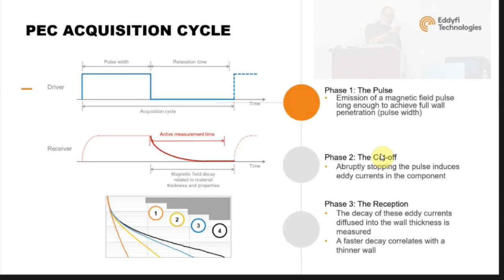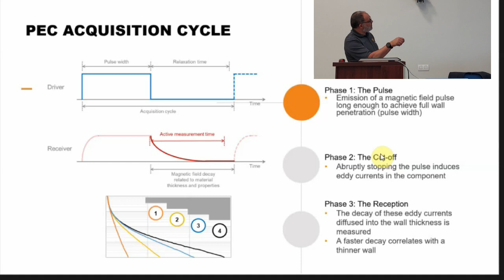So as I say, you have a pulse on your coil creating a magnetic field. When we stop, we are measuring the time for the eddy current to vanish. And you see at the bottom an illustration. I don't know if this works or not. It does. So you have different thicknesses here, from the thicker to the thinner, and then you have the slope of the curve linked with a particular thickness.